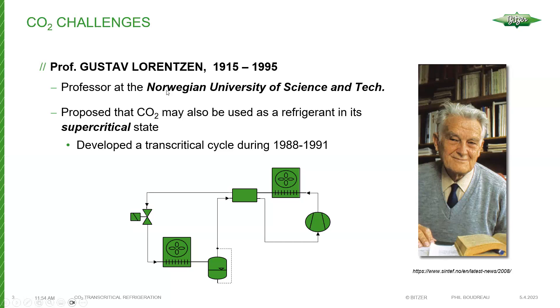Professor Gustav Lorenzen at the Norwegian University of Science and Technology proposed that we could use CO2 refrigerant in its supercritical state. He asked why we're so focused on subcritical refrigeration when CO2 is a very good refrigerant. One of its main drawbacks, aside from operating at high pressures, is that you would have to operate it in a supercritical state. So he worked towards producing systems that can operate supercritically — or transcritically, as they call it. Transcritical simply means the compressor in the system is transcending the critical point, which for CO2 is approximately 88°F.